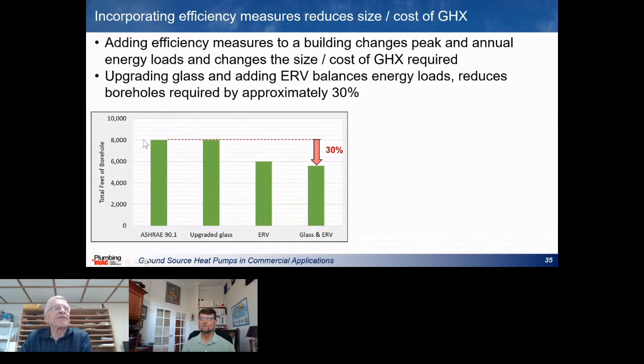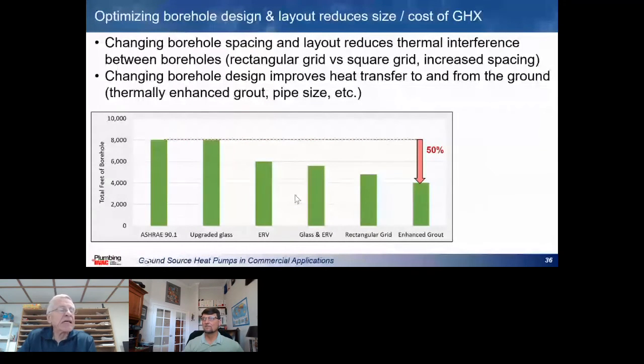If you're looking at 8,000 feet of drilling times, let's say $30 a foot, that's a big deal. 240,000 bucks. Now we're down to 180,000 bucks. Knock it off a little bit farther when you add both of these components. What happens if we look at the design of that ground heat exchanger itself? Changing the borehole spacing.